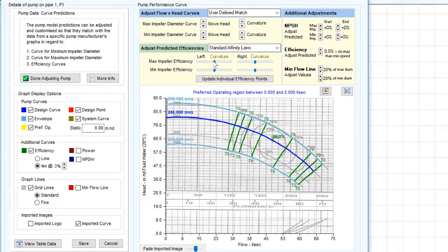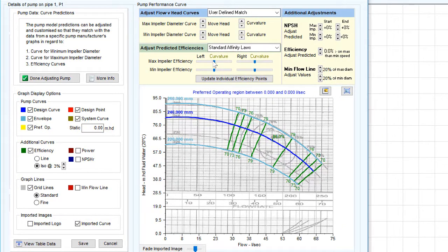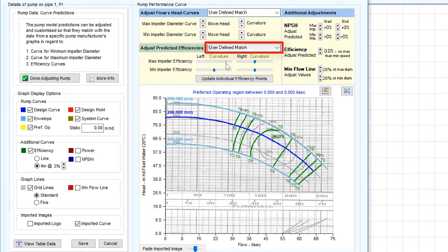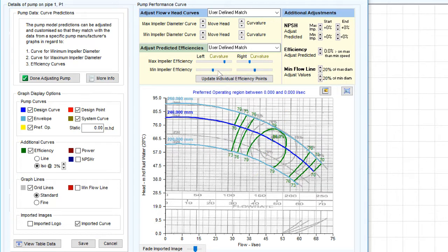The Adjust Predicted Efficiency options allow the predicted efficiency values to be modified. Further adjustment can be made to the data so that the ISO efficiency shape selection type will become a user-defined match. The best efficiency point on the base data performance curve is used to divide the performance graph into different areas, and the slide adjustments allow the curvature of the groups of ISO efficiency lines to move as a block to the left or right.